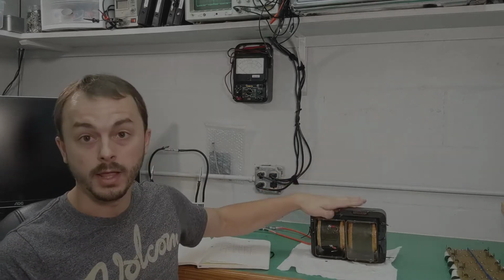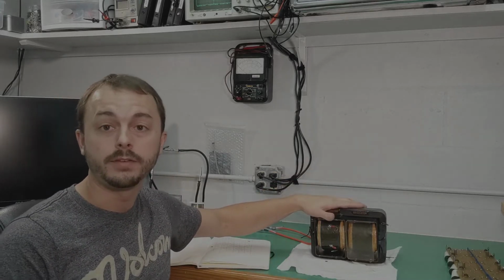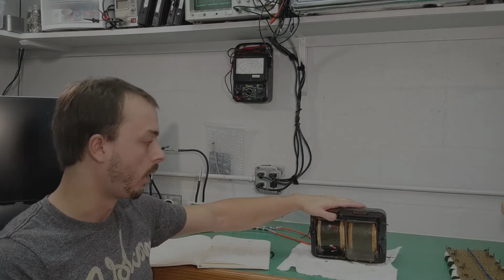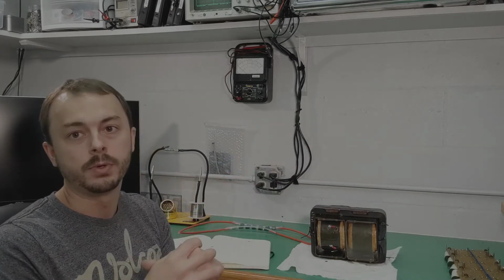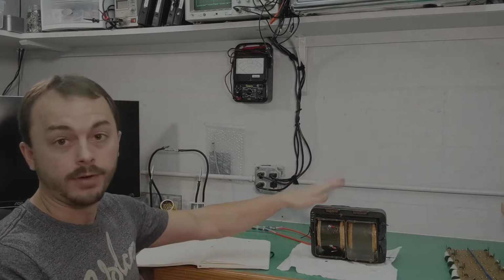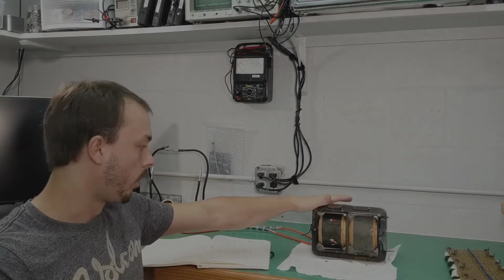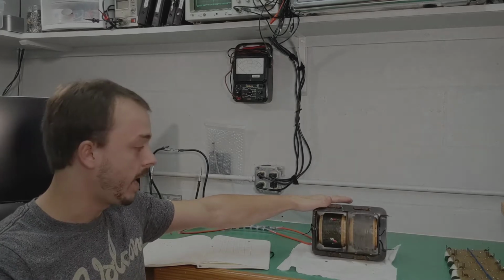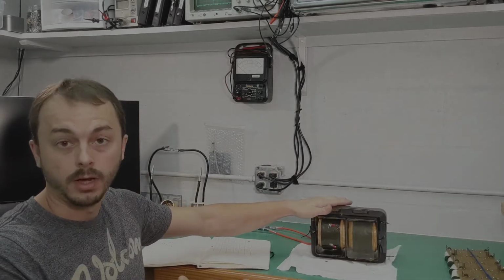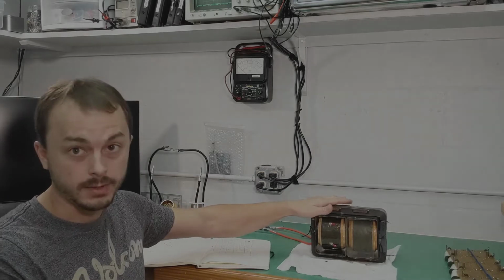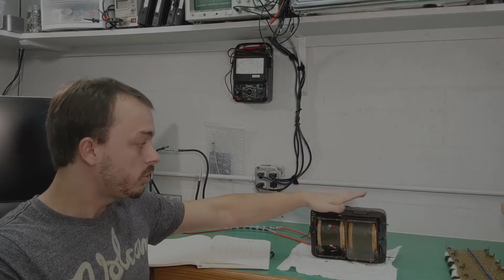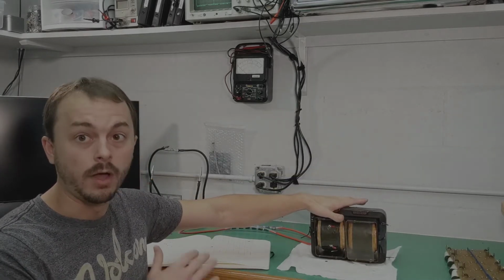An X-ray transformer is designed to make 50 to 100,000 volts for powering an X-ray tube for dental units or the doctor's office. This is a very old unit, an iron core X-ray transformer that will take in 120 volts AC and step it up to 100,000 volts. It has a bunch of different windings on this core.